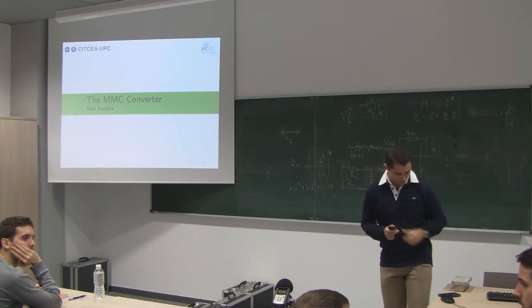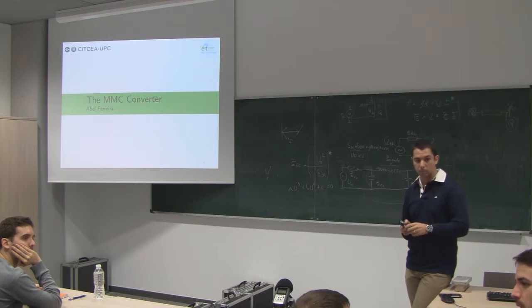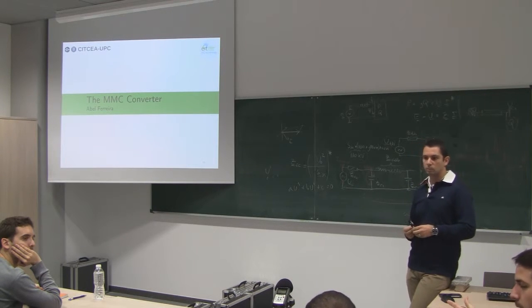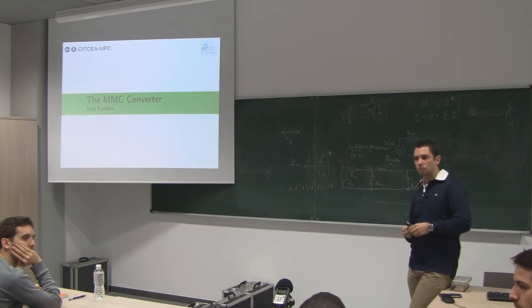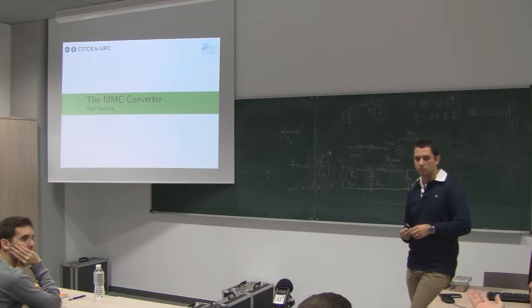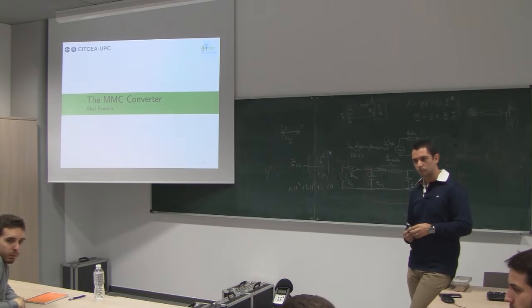I think XLPE cables are used for VSC technology, and mass impregnated cables are used for LCC technology. Since they are two different technologies, they are still evolving the XLPE—it's quite a new technology used for cables in this application. So they are still pushing it. That's the limit on voltage, and the limit on power. I don't know exactly the ratings of the IGBTs and the current you can handle through the cable, but I think it's around 2 kiloamps, something like that. That's the benchmark numbers: plus minus 400 kV and up to 2 kiloamps.